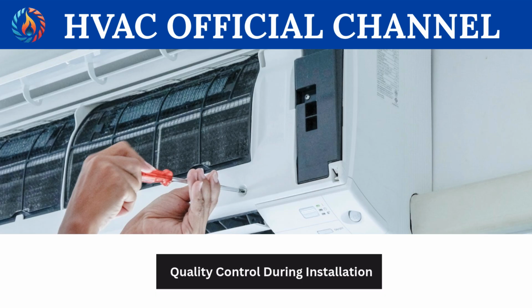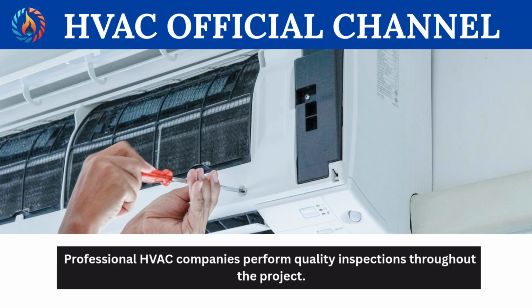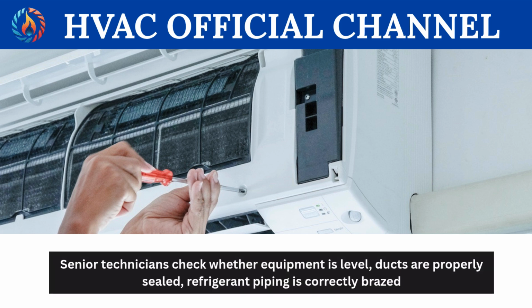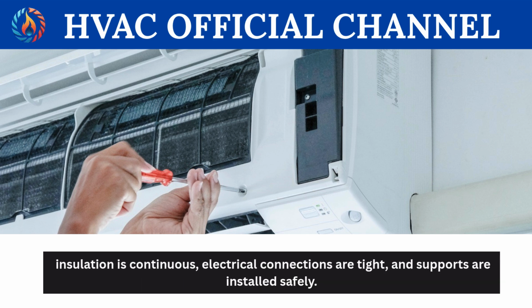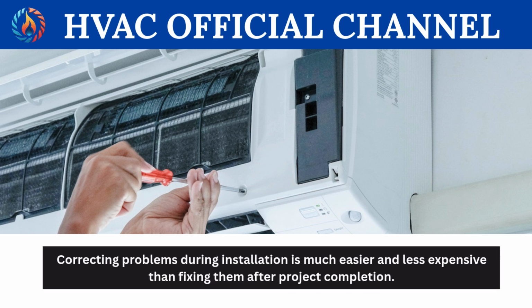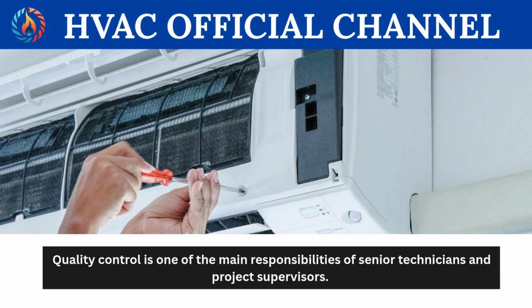Quality control during installation. Professional HVAC companies perform quality inspections throughout the project. Senior technicians check whether equipment is level, ducts are properly sealed, refrigerant piping is correctly brazed, insulation is continuous, electrical connections are tight, and supports are installed safely. Correcting problems during installation is much easier and less expensive than fixing them after project completion. Quality control is one of the main responsibilities of senior technicians and project supervisors.